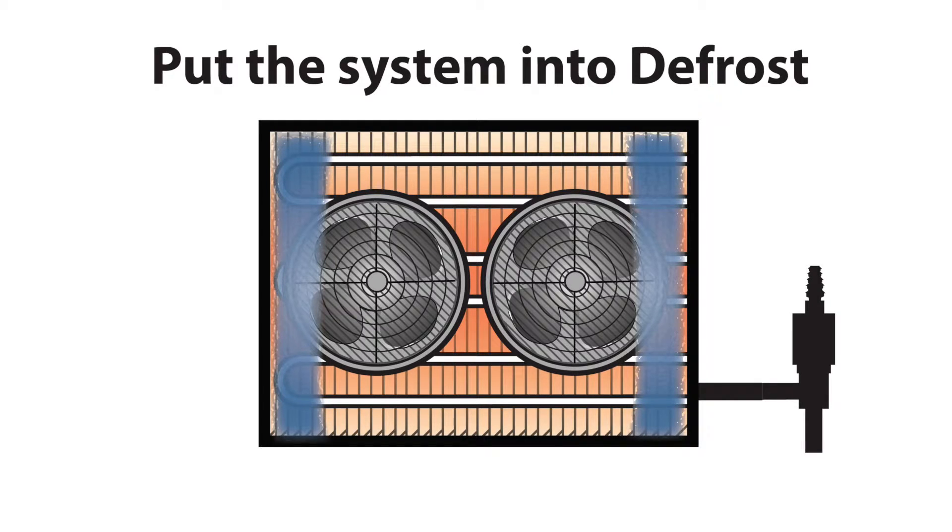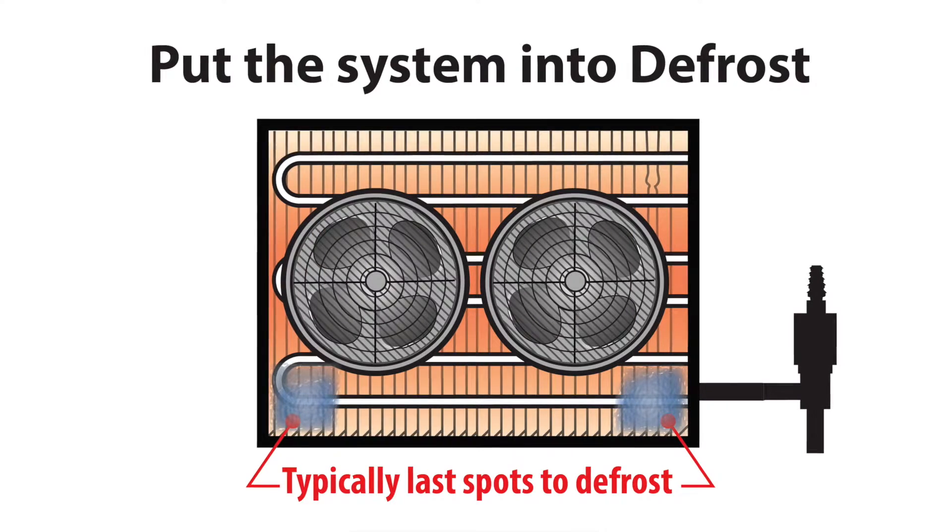To determine the most appropriate coil sensor location, put the system into defrost. The coil sensor location is easily determined by viewing the frost pattern during the defrost.